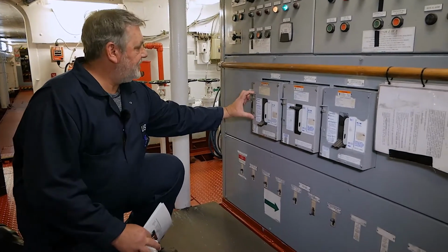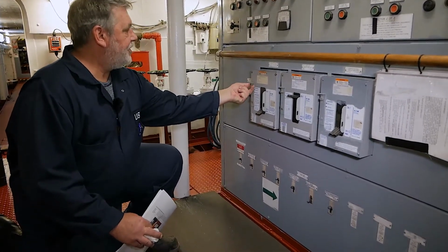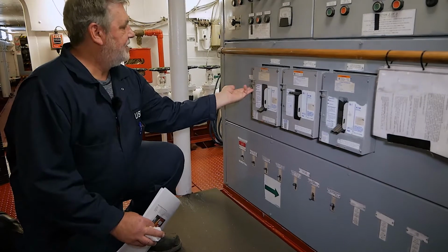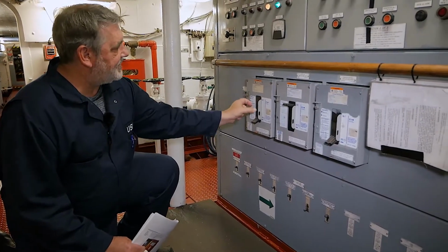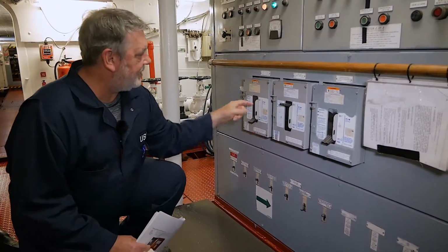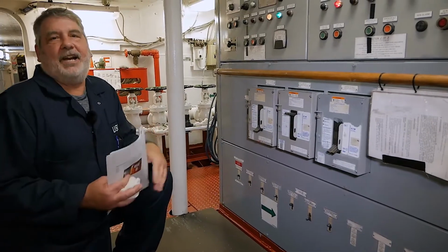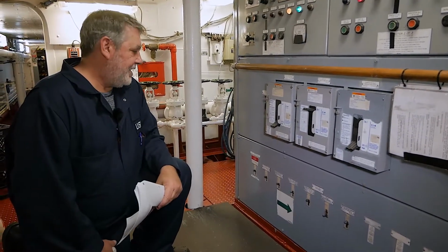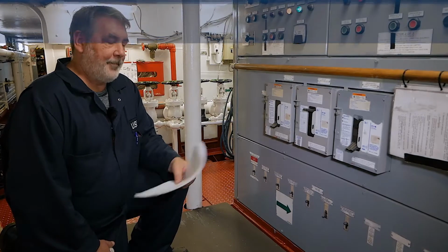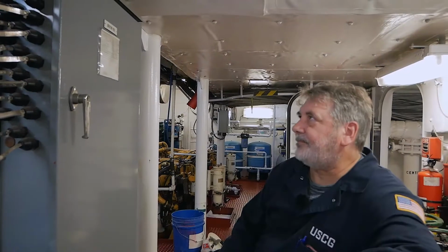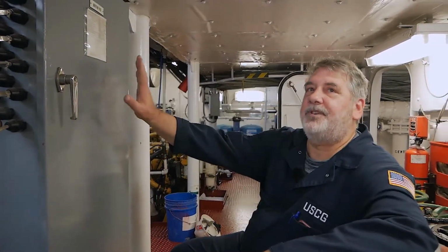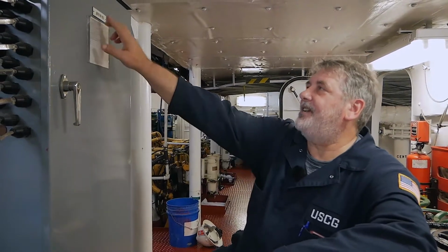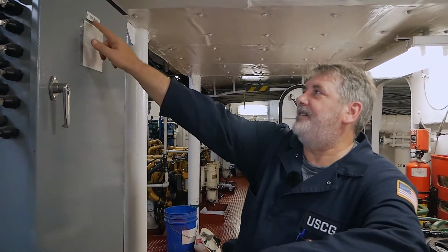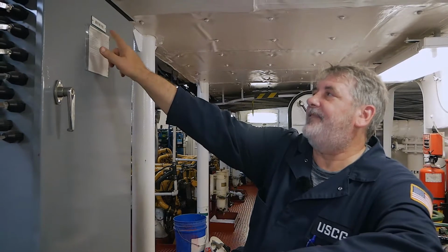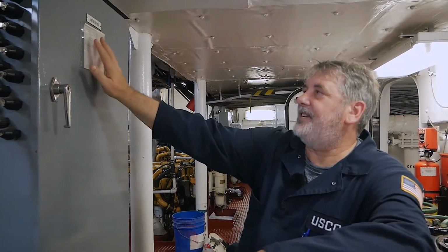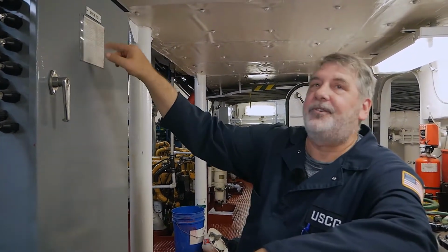As you can see, this metal arm here, you can undo this holdback, rotate this down, and you can put a lock on it to prevent energizing this breaker. That's a good safety feature. Okay, distribution panels. As you can see, the distribution panel has a name tag identifying it. We also see an external breaker directory posted.